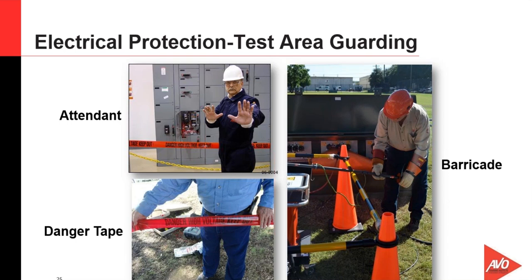The picture on the right is a little different. This is a picture where the test area is barricaded, but within the test area, there's another area being barricaded. This is a coupler for a partial discharge test set that's in this test area. The corona rings at the top of the coupler become energized, so even with the test area secured, it may be necessary to secure a specific piece of equipment itself, and in this case, of course, barricading was the solution to that.